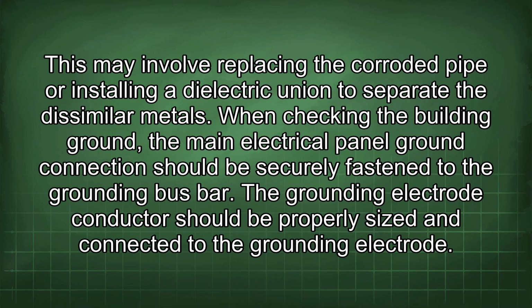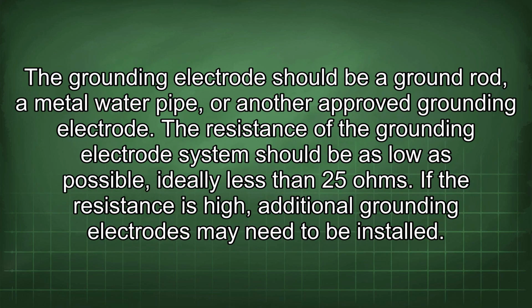When checking the building ground, the main electrical panel ground connection should be securely fastened to the grounding bus bar. The grounding electrode conductor should be properly sized and connected to the grounding electrode. The grounding electrode should be a ground rod, a metal water pipe, or another approved grounding electrode. The resistance of the grounding electrode system should be as low as possible, ideally less than 25 ohms. If the resistance is high, additional grounding electrodes may need to be installed.